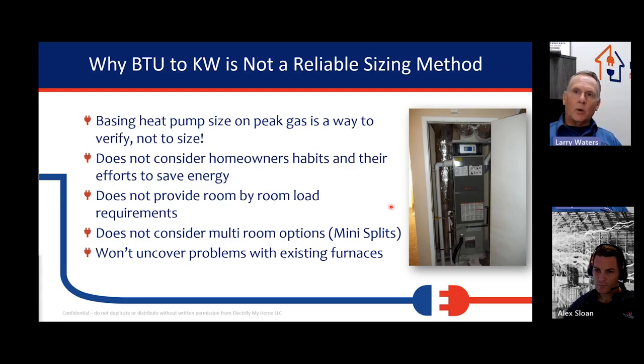Okay. Why is BTU to kilowatt not a reliable sizing method? We're seeing this out there of what they call peak heat or peak gas, and sizing a heat pump for the peak gas usage for a month. Now, it's a good way to verify a regular load calc, but what it does not do is consider the homeowner's habits and their efforts to save energy. So as air conditioning and heating people, we know we've gone to people's houses. They say, I haven't used my furnace a lot because I don't like burning natural gas, or the bill's been really high. So if they didn't run their system a lot the year before because they were conserving energy, and we matched their heat pump to the peak BTUs, and their peak BTUs are artificially low, that's not going to give us a good match.